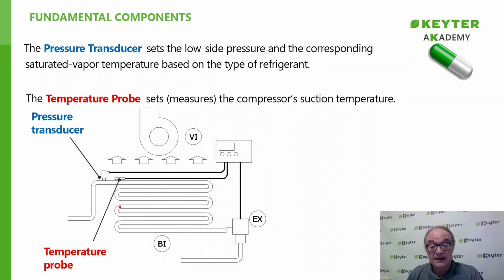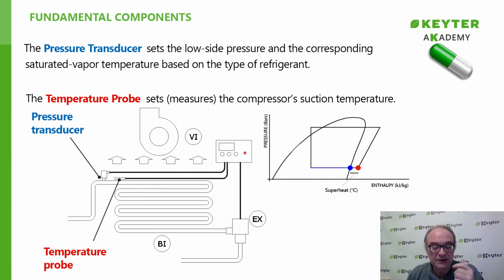Well, the team is well informed about the refrigerant we are working with. We have provided them with the necessary information regarding the specific refrigerant, including details about the complete hood and the entire Mollier diagram. By knowing the pressure, they are able to determine our location, and they also know the saturated vapor temperature at the evaporation pressure. Using a temperature probe, they can accurately determine the temperature at which we are discharging the refrigerant gases from the evaporator. As a result, the superheat, which is the difference, is obtained directly.